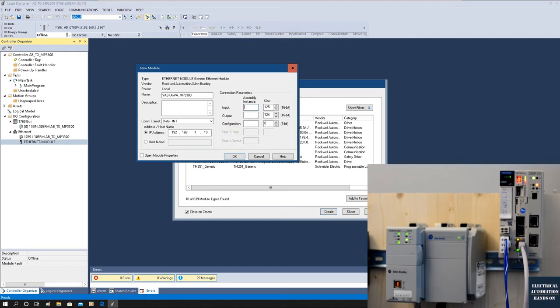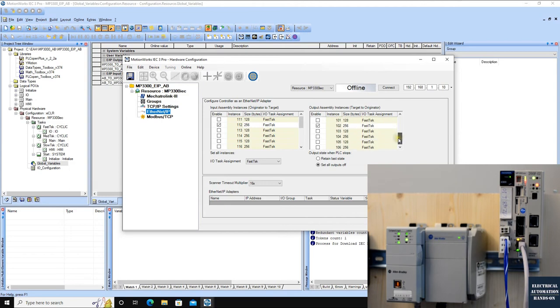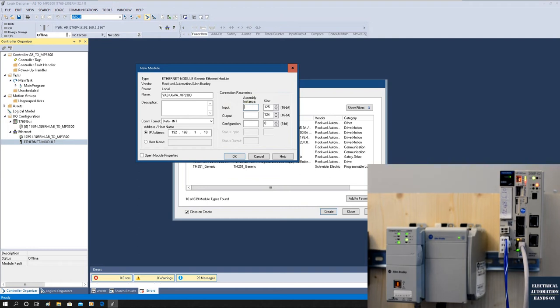Going back to the Yaskawa hardware configuration: the target-to-originator instance (data from MP3300 to Allen-Bradley, adapter to master) is instance 102 — this will be the input assembly on the Allen-Bradley side. The originator-to-target instance (master to adapter) is instance 112 — this will be the output assembly. So in Studio 5000, set Input Assembly Instance to 102 and Output Assembly Instance to 112.